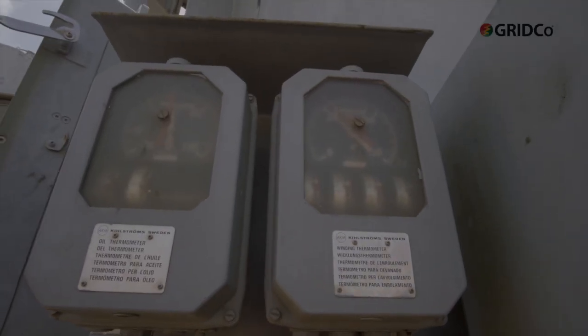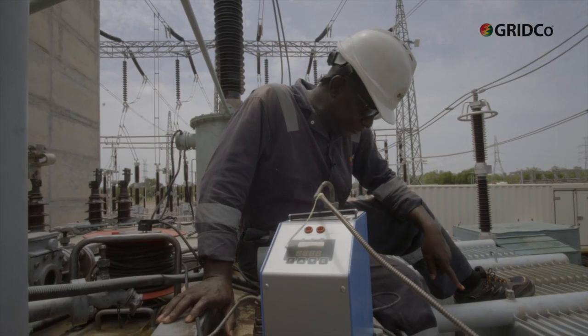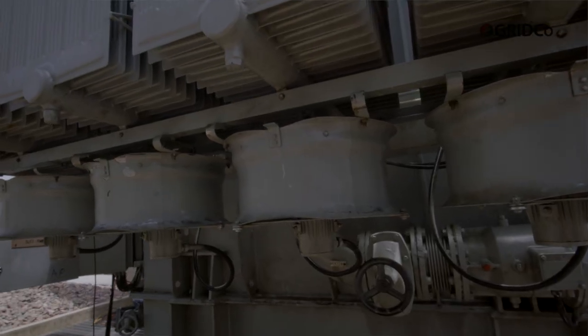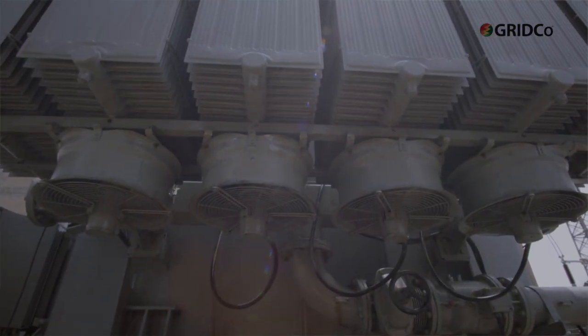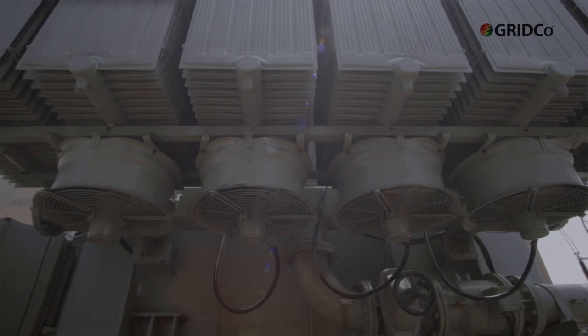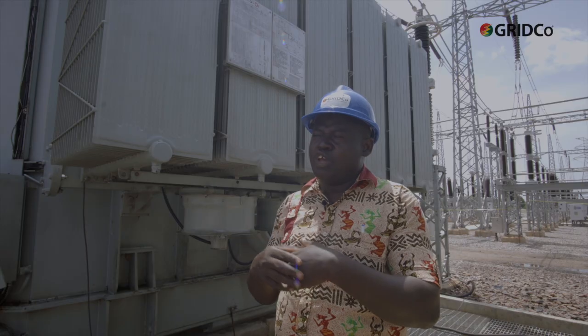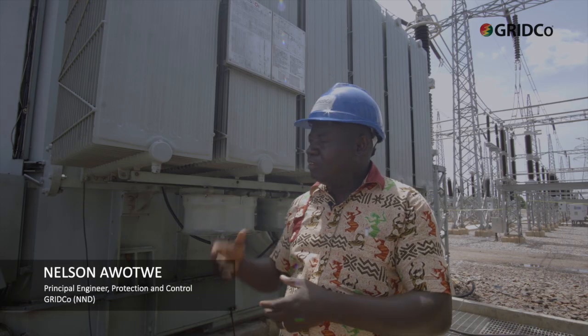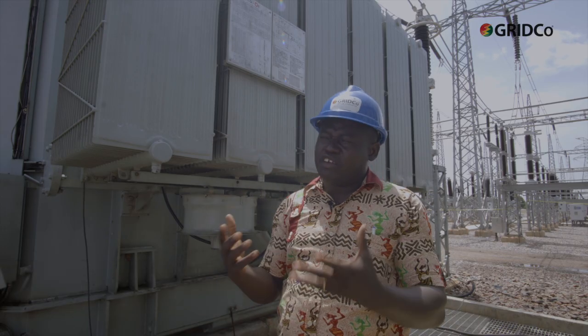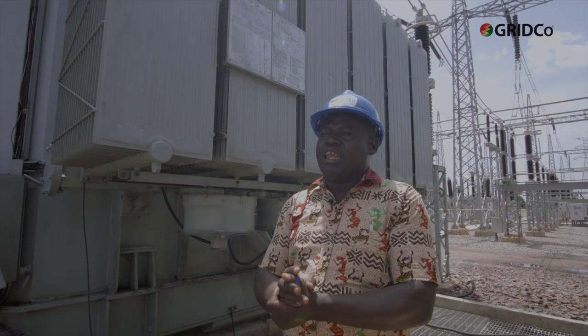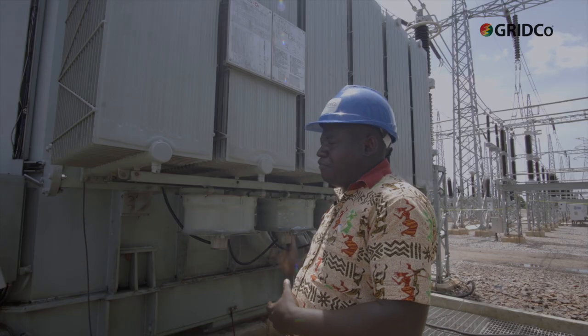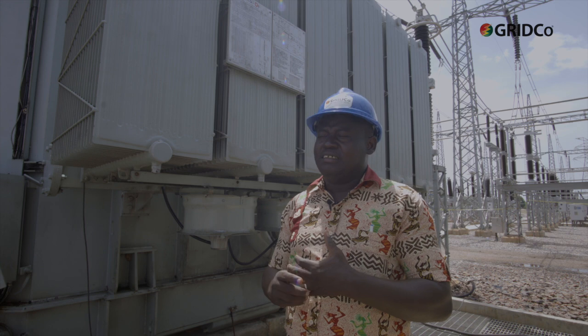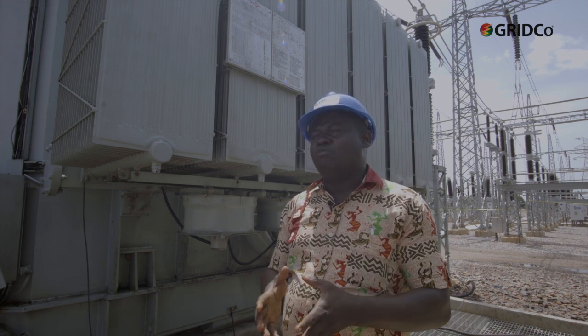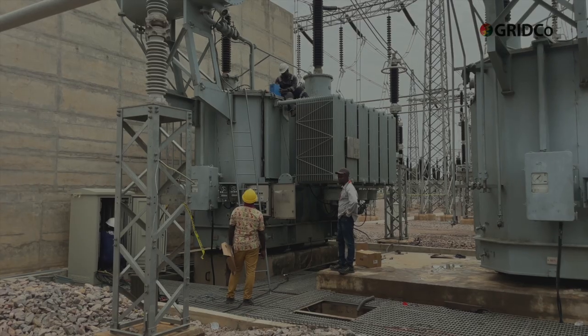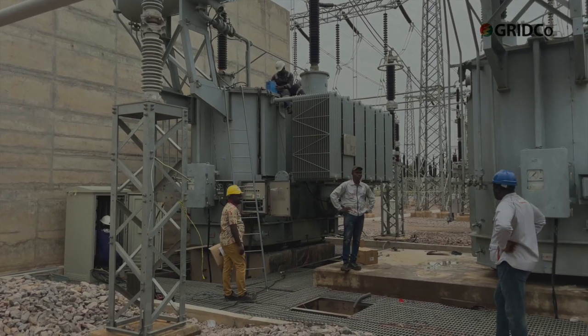When the temperature rises up to 70, then the fans which are under these radiators will come on. The group 1 will come on to cool it. The transformer's cooling depends on the type of load. Between 0 and 25 MVA, you are using the oil natural, air natural. The oil is the one that is cooling the windings of the transformer up to 25 MVA. Now, if you move beyond 25 MVA, the fans will come on automatically. So beyond that 25 MVA, you have now moved from oil natural, air forced. So the fans come on and then force the cooling.